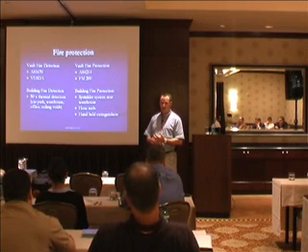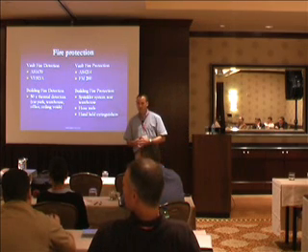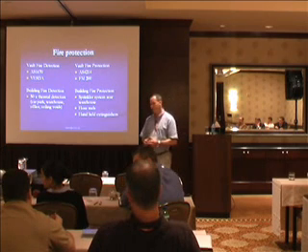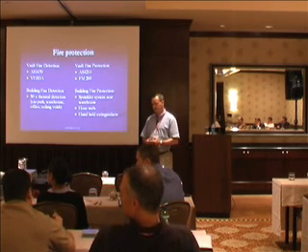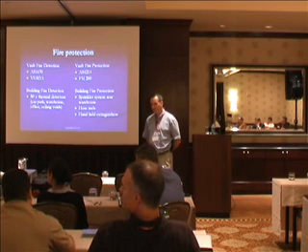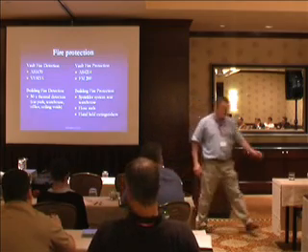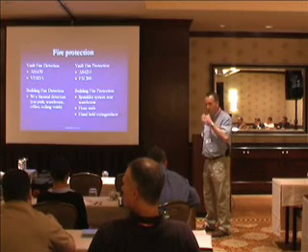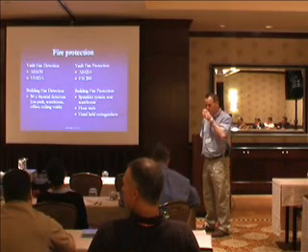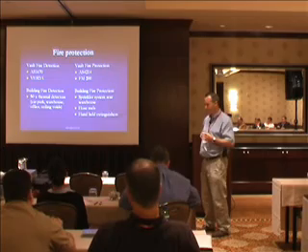What about backup of that drain? Well, if you do this, you need to have a backflow valve on it, because you've got to prevent the backup. If the sewer system backs up... There's a vault in Louisville, Kentucky, that was below ground level, and the drainage ditch nearby got stopped up with a big stump. The water overflowed and came up 18 inches in the vault through the floor drain. So you need a backflow valve for that.